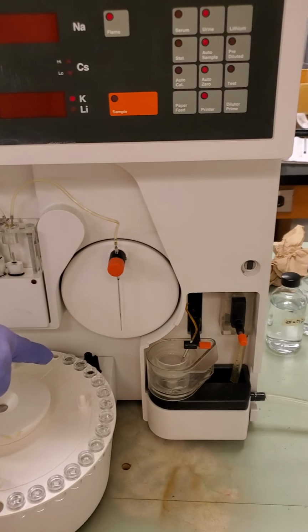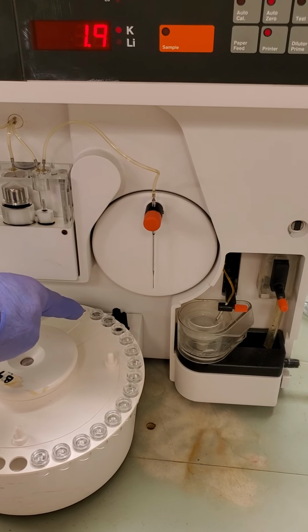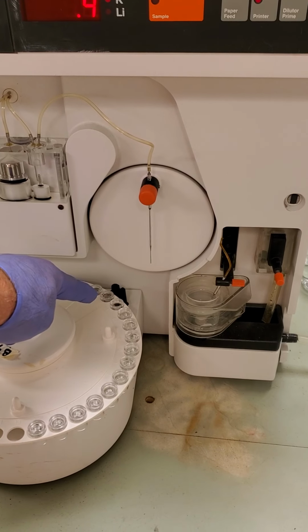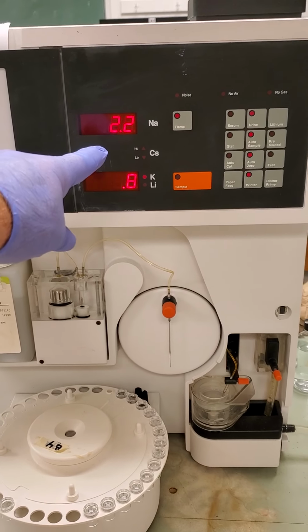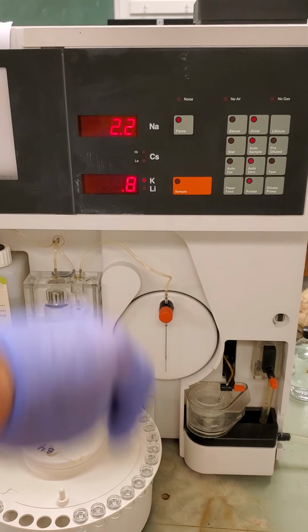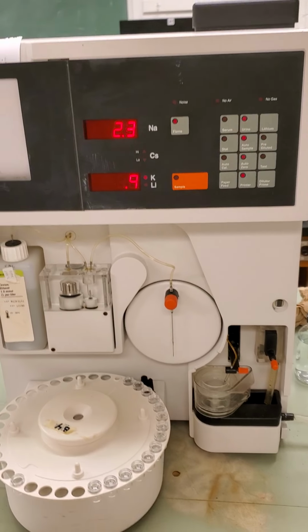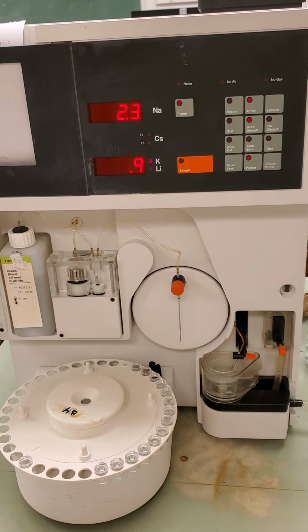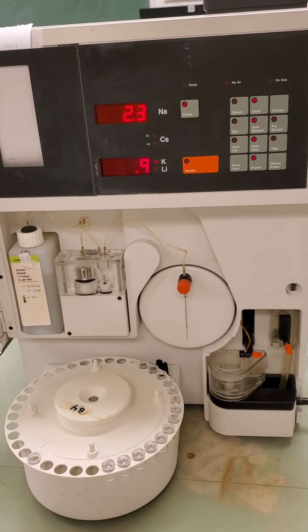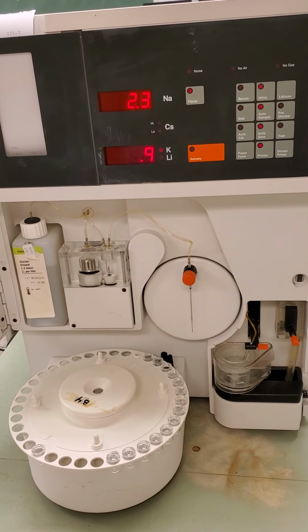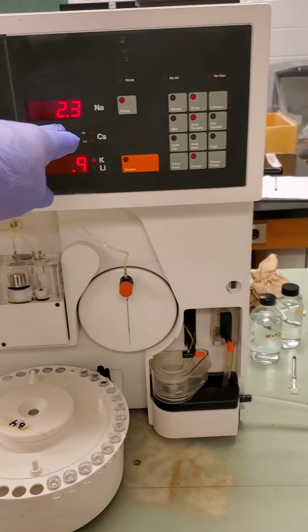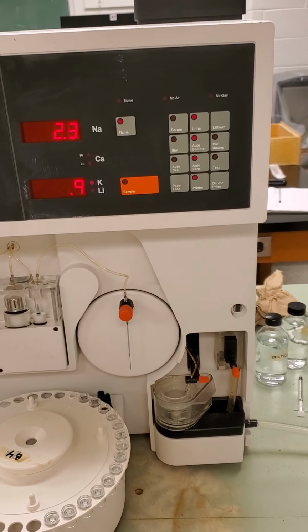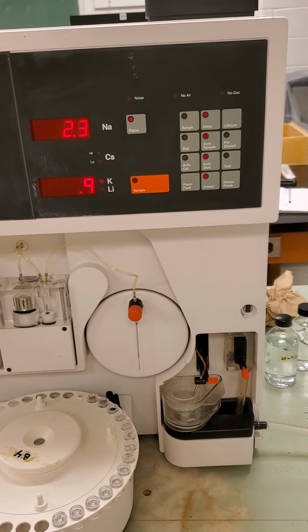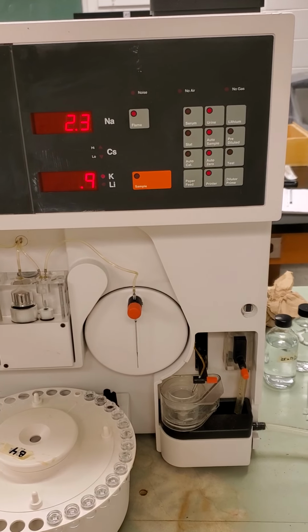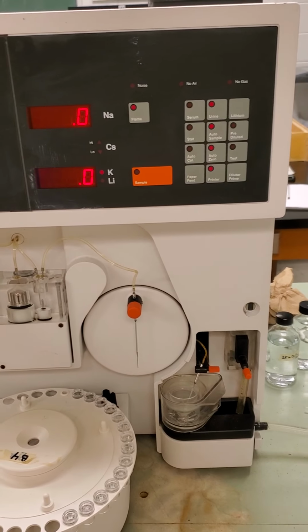So it's just read in the 100 now distilled water, which is 0. So it nulls it to 0. You saw previously it nulling it to 100. So sooner or later, that's going to come up as 0. Now, if there's too much sodium in the water, you may get this failing. And 2.3 is kind of high. But okay, it was happy with that.